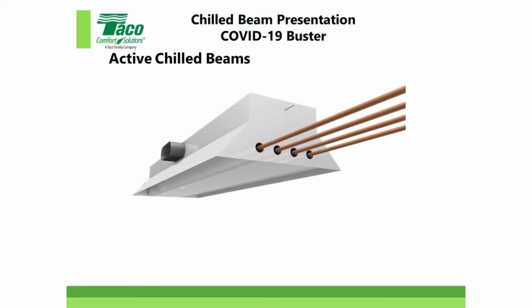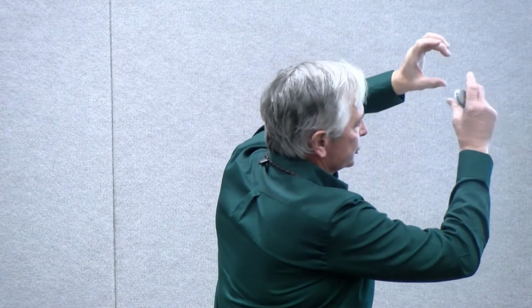Here's the more prevalent one now, what we call the active chilled beam. You see the little connection on the far left; that's where the primary air comes in, the dry primary air. This one happens to be a four-pipe, so it can be heating and cooling. There are coils in there, and roughly two-thirds of the coil in a four-pipe would be cooling and one-third heating. That could be a little different for different manufacturers, but that's how it's set up there.